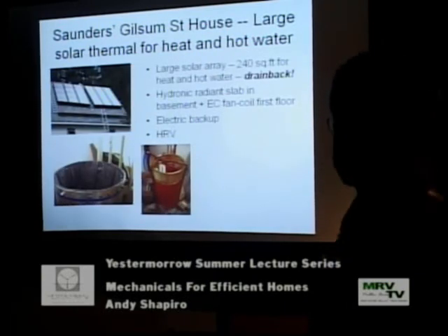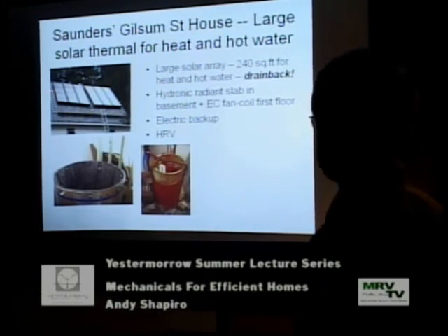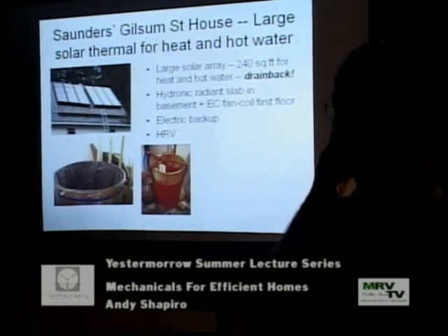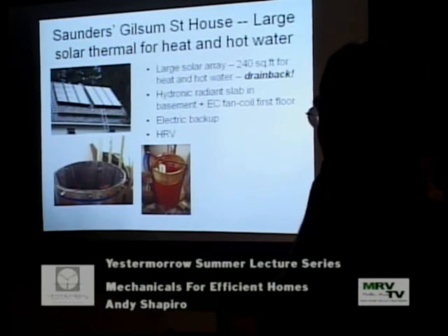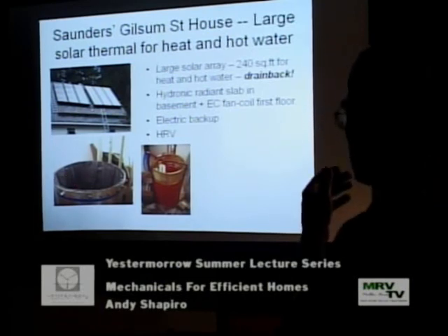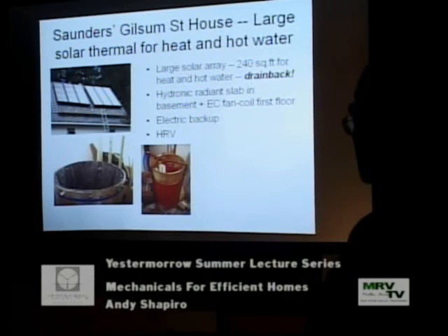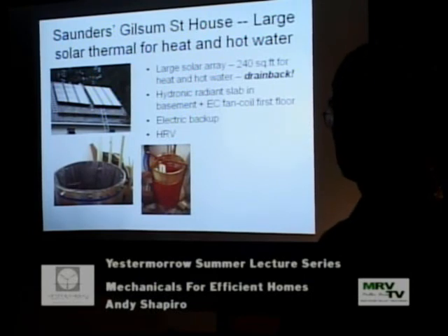So we did a big drain back system. This is a soft tank in the basement—I think this is a 600-gallon tank. So it's a drain back. This is atmospheric; it's got a lid, but it's atmospheric pressure. You pump water up in here when there's heat, and when there's not, it all drains back into the tank. And there's heat exchangers in it to pull out domestic hot water and pull out space heating.